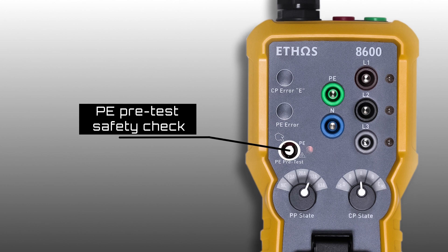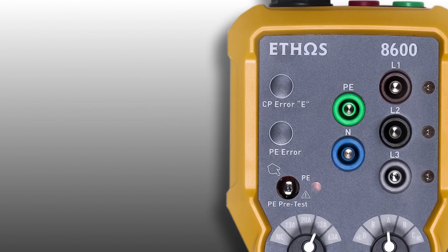PE pre-test safety check. This is to check if there is any dangerous voltage on the earth. If a red neon illuminates, stop the testing procedure and investigate further.